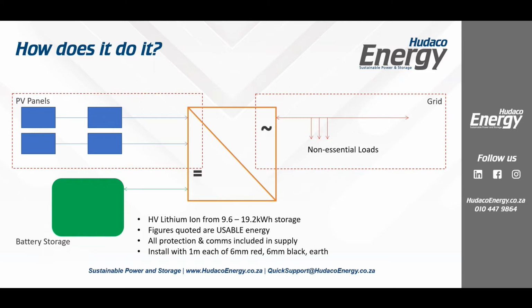All your protection and your communications are included in the supply box. So this includes your DC breaker, which slides into the side. It includes your communications cable. It includes your wireless dongle so that you can communicate with your home network and see everything on your phone, your laptop, your computer. That all comes in the box for you. And all you need to supply with this is about 1 meter each of red, black, and earth cable, 6 millimeters. The fact that it's a high voltage lithium ion system means that we don't need to have 25 mil DC cable. We don't need to have big fuses.